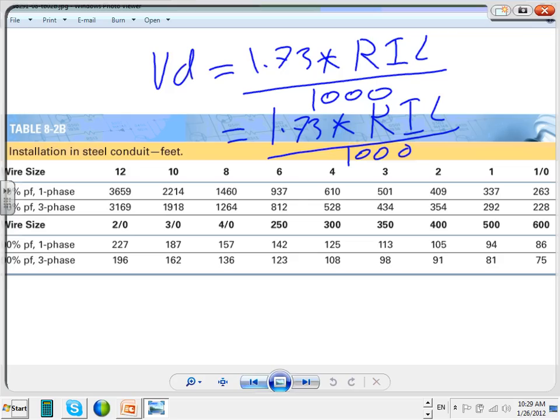I'm going to start with the number 20 amps. Can you guys go all the way to 20 amps in the last column on the right side, the first from the right on page 1-23? 20 amps on number 12 on page 1-24. If you go to the middle of that table and look at 20 amps on the right hand side, and number 12, how far can I pull a load that's 20 amps if I'm wiring it with number 12? Can you guys see? 70 feet.